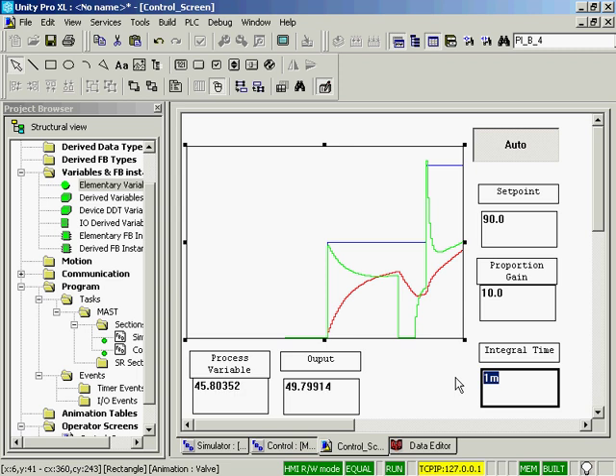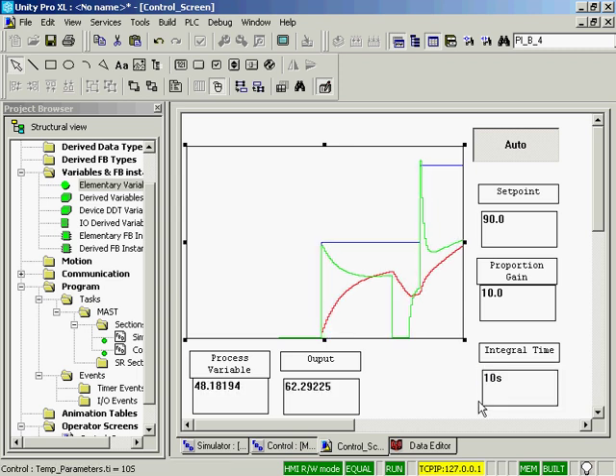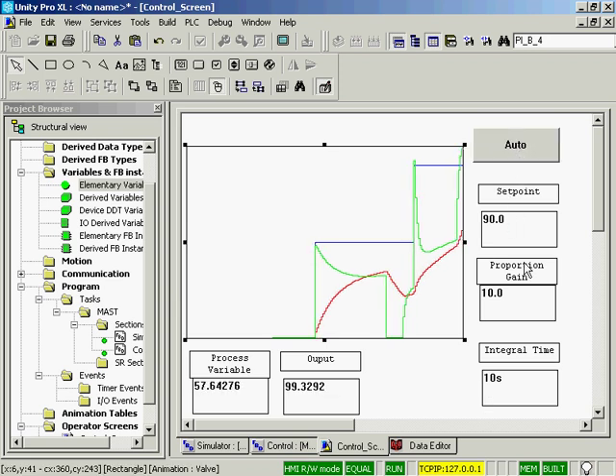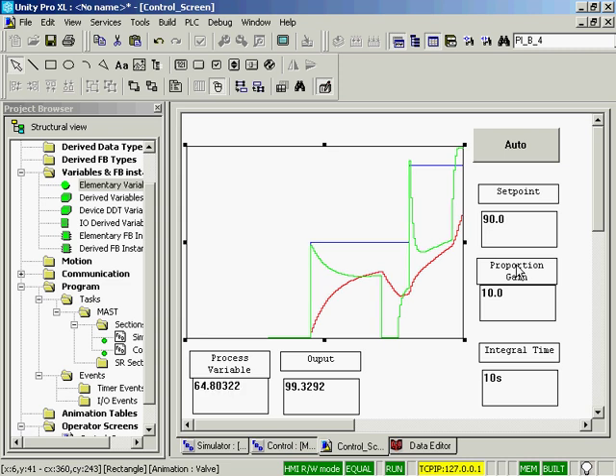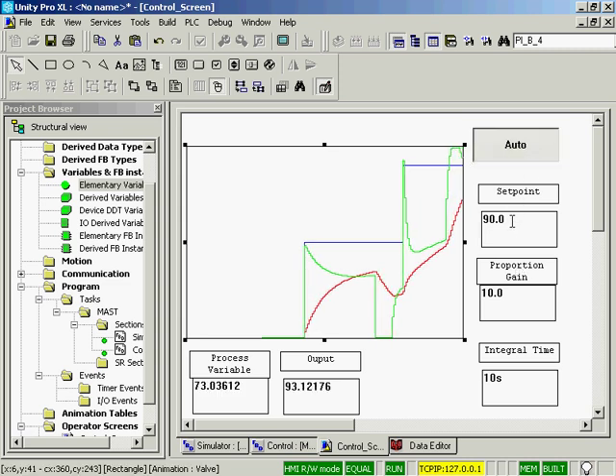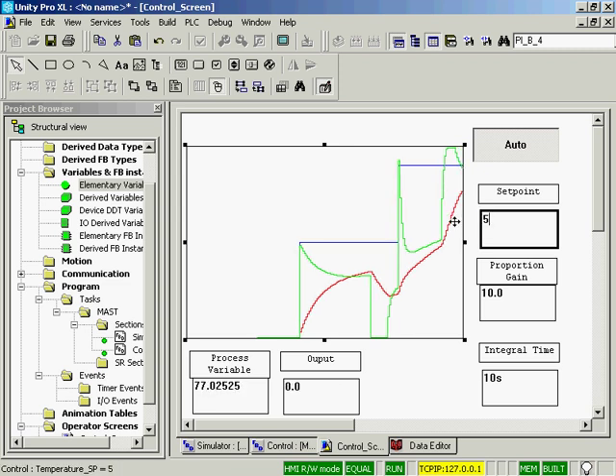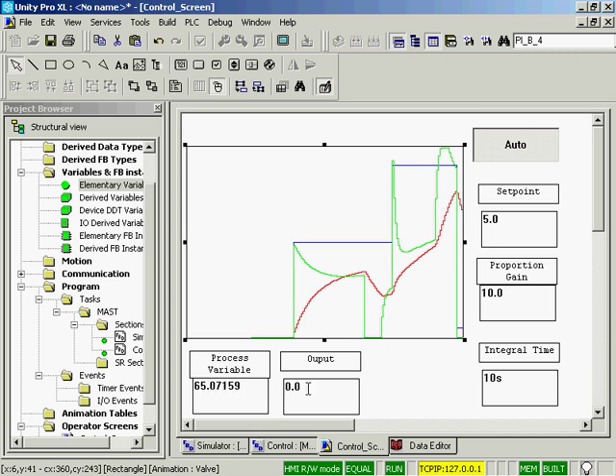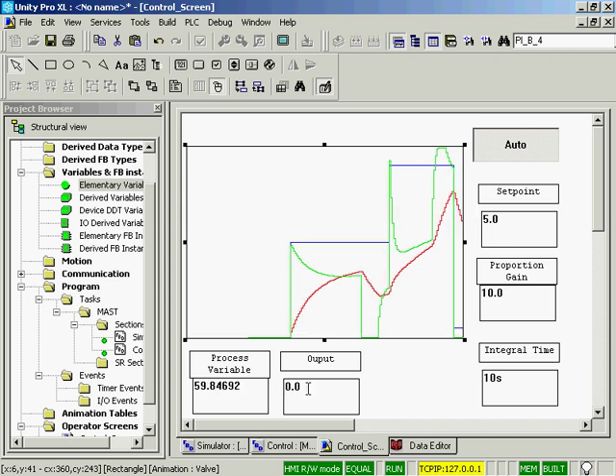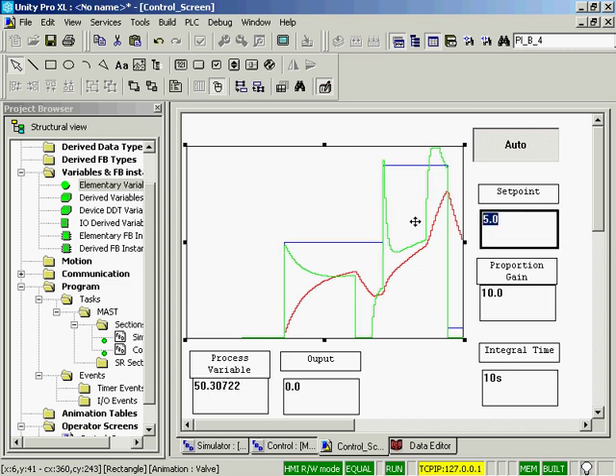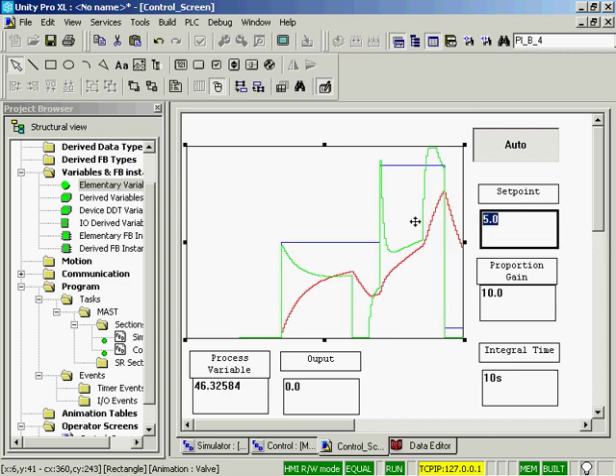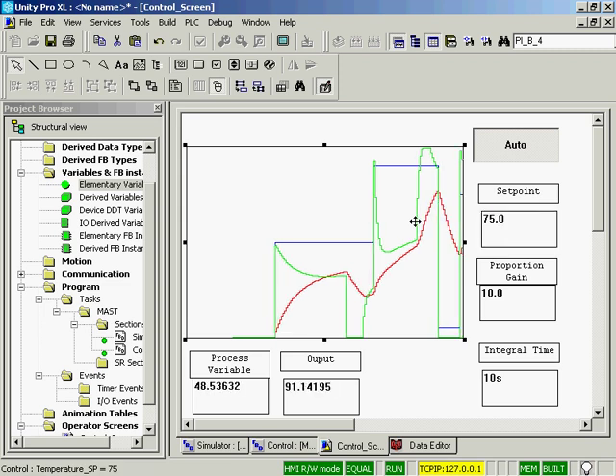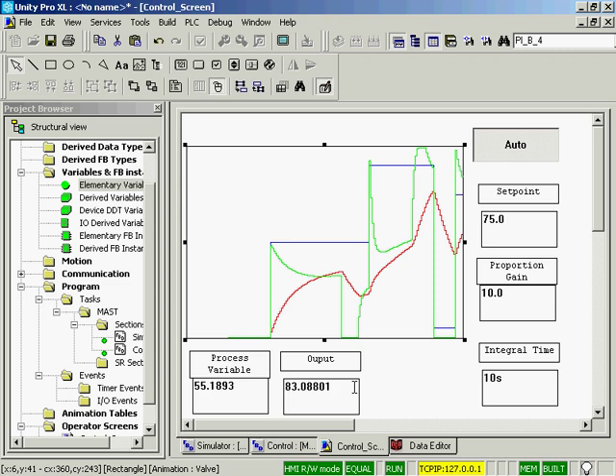So now let's change the integral time down to 10 seconds. We'll take it out of auto, put it back in auto. We'll change the setpoint down to 5 and notice the output went down to zero. We'll change the setpoint back to 75 and you'll see that output go to nearly 100.